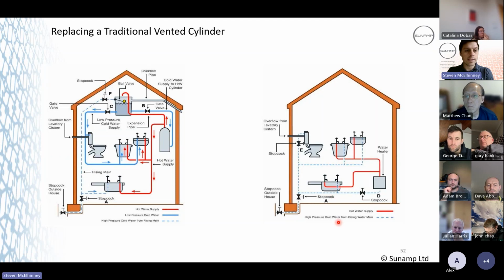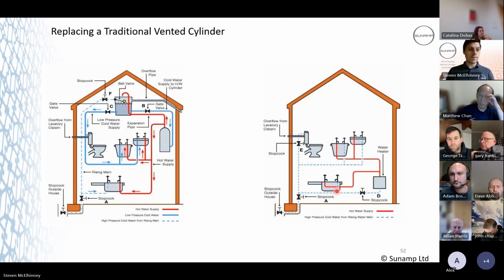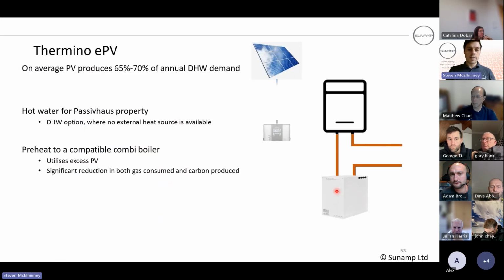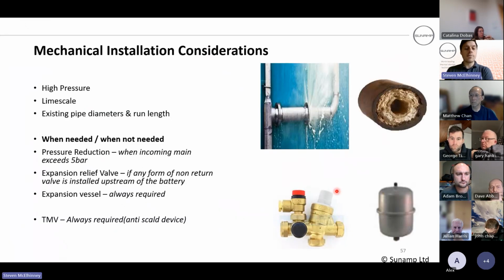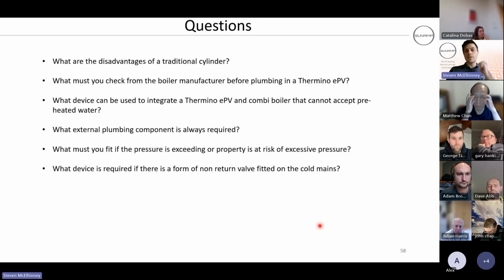Does that make sense for everybody? Because we get a lot of calls and people get hung up on thinking they've got to have the pressure relief valve beside the battery, and where am I going to terminate? I'm going to have to lift the floors and everything else. But you can fit that anywhere, as long as it's downstream of any non-return valve and upstream of the battery, you're fine. So that's another thing as well. If you think that the property has a non-return valve for any reason, we do recommend having that expansion relief valve fitted, again downstream from the non-return valve and upstream from the battery. Your pressure reducing valve, that's a non-return valve, isn't it? So just a couple of installation considerations to bear in mind.